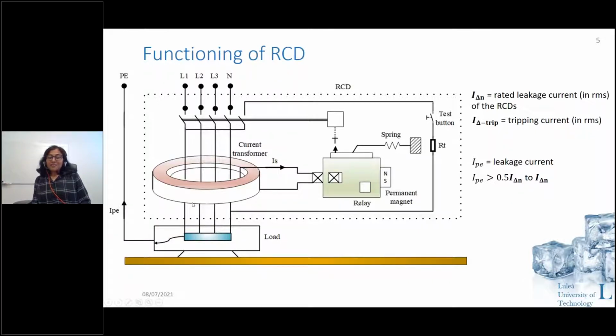In case of unbalance between the three phases and neutral, there will be a leakage current. There can be some unbalance even in steady state condition, and of course, if there is an earth fault, there is an unbalance. So there will be some leakage current during a fault condition. In either of those conditions, a magnetic field is induced and you have a secondary current IS. This secondary current, when it reaches a predetermined value, opposes the magnetic field of this permanent magnet, and the armature connected to the yoke is pulled by the spring and the RCD trips.